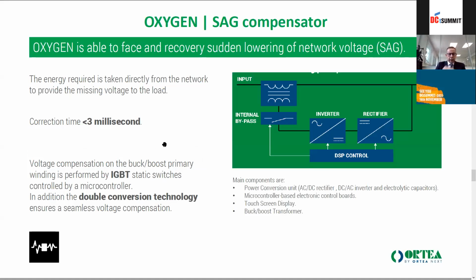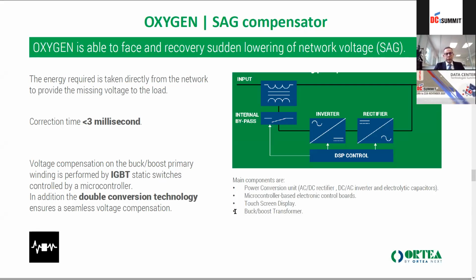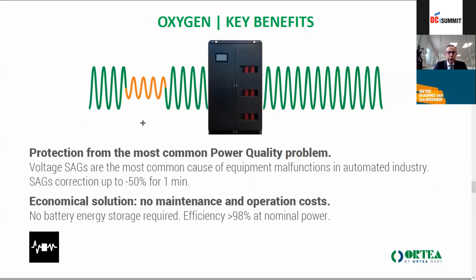So the oxygen is an instrument which is a voltage stabilizer in reality, working on a normal variation, but it can also, within 3 milliseconds, so less than a wave of voltage, compensate what is missing till minus 50%. So if you have a SAG till minus 50% on a line within a wave, the oxygen SAG compensator will be able to give you always a steady output.